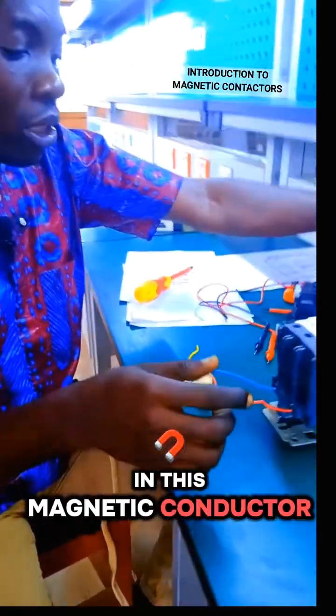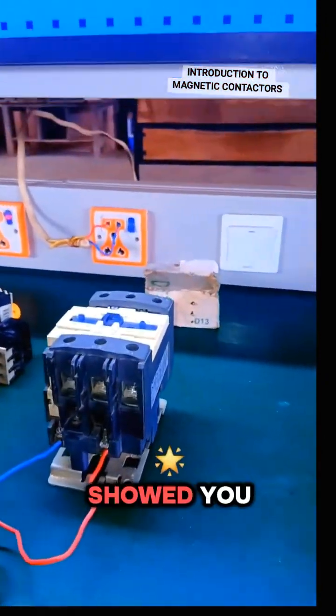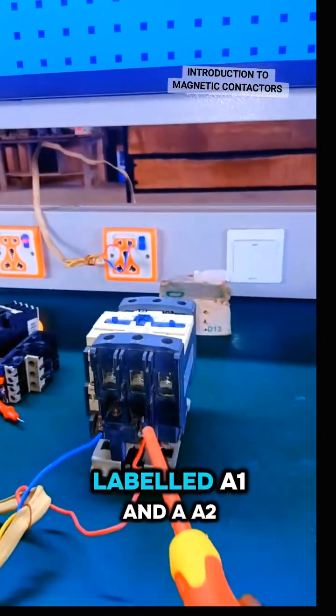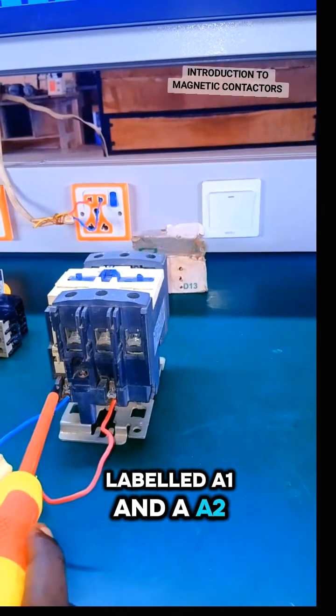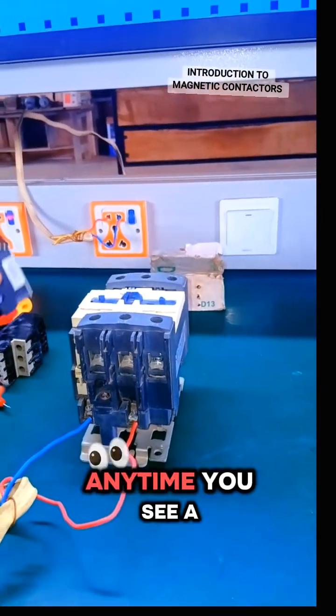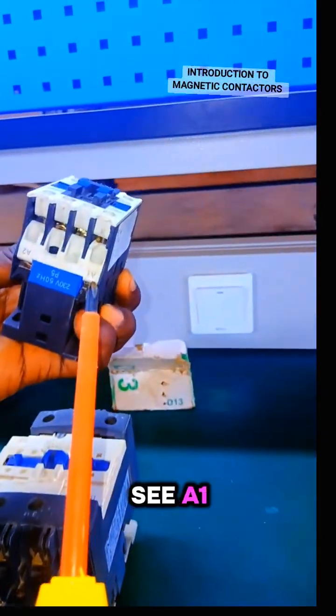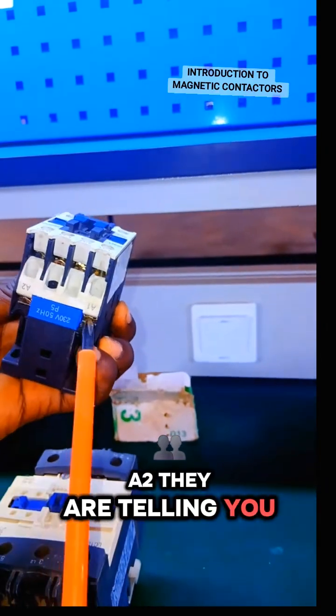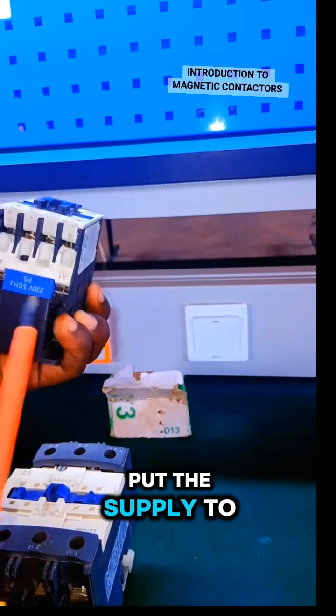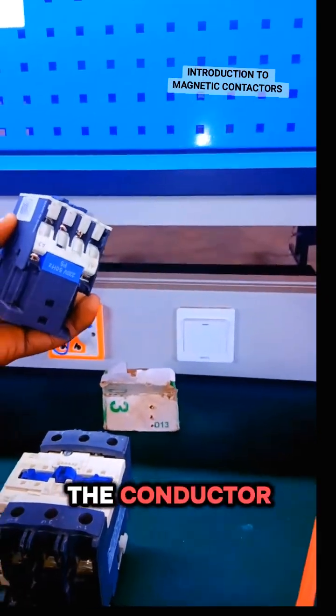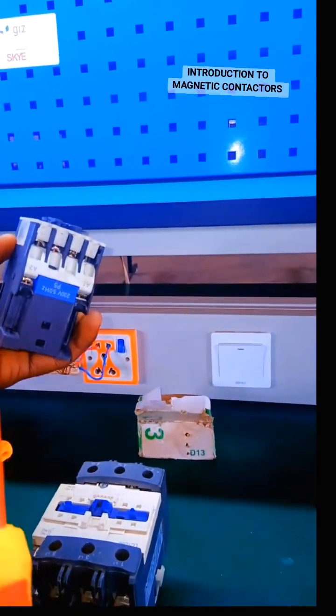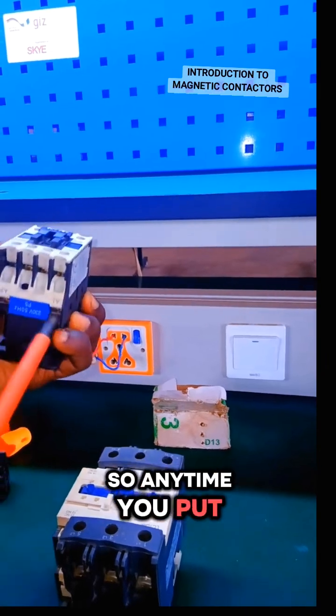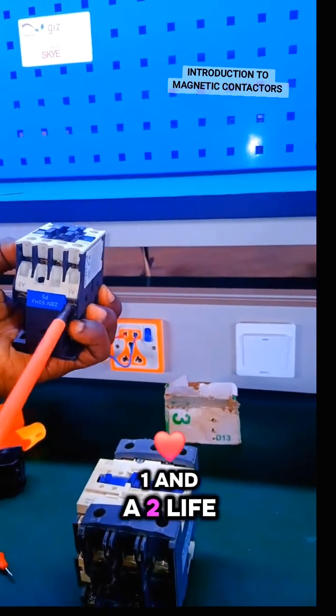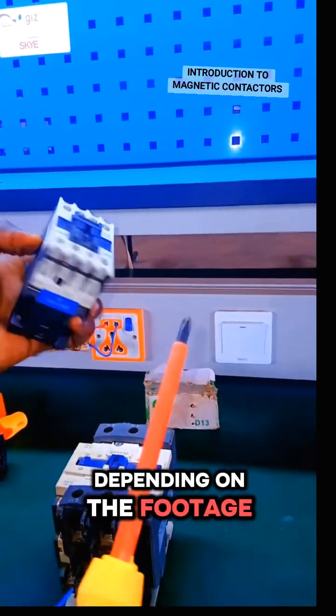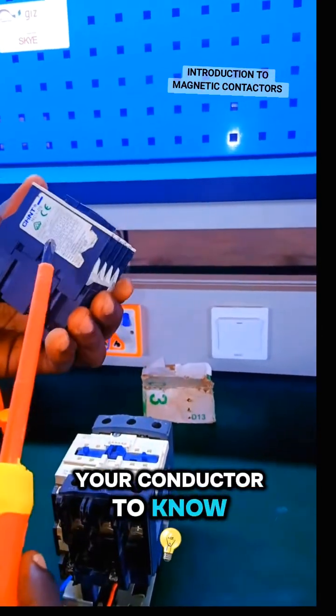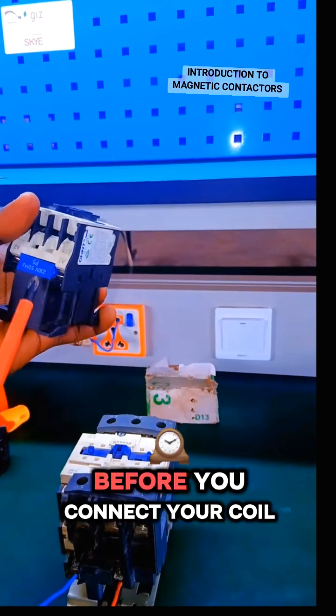In this magnetic contactor, you can see the coil that I showed you. These coils are normally labeled A1 and A2. Anytime you see a magnetic contactor and you see A1, A2, they are telling you that is where you are going to put the supply to energize the coil of the contactor. The coil is of lower rating. So anytime you put the supply at A1 and A2, live and neutral, depending on the voltage, you need to check your contactor to know the operating voltage for the coil before you connect your coil.